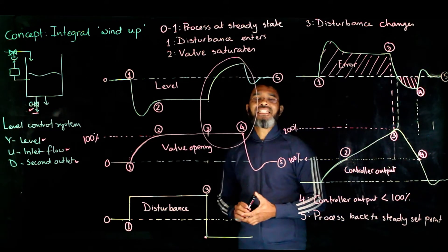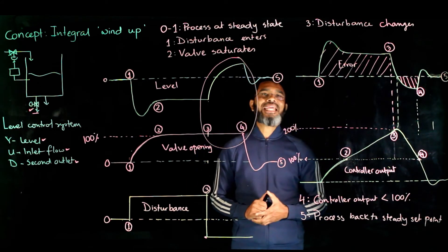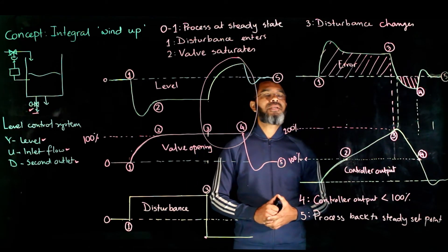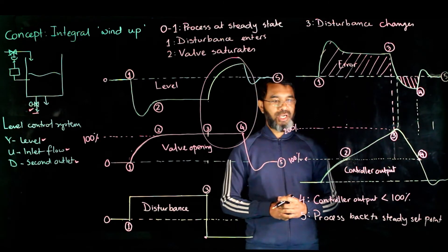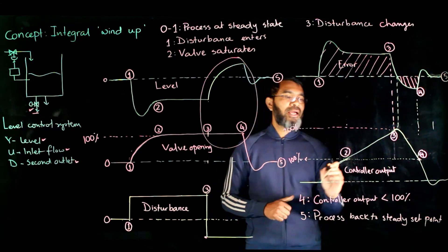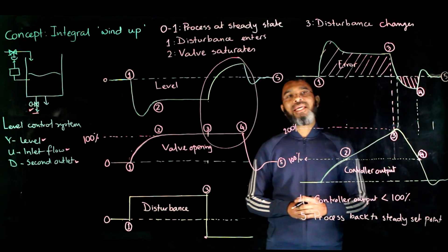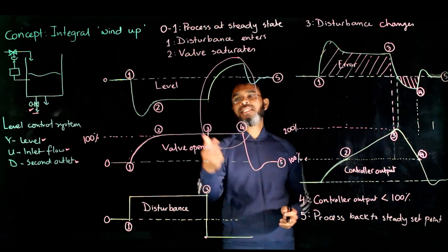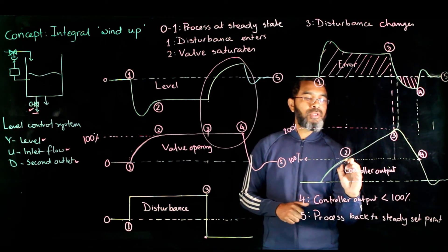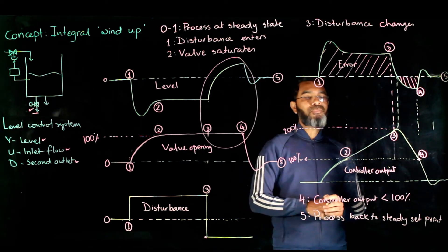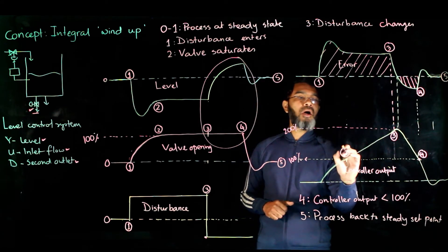This is the concept of integral windup — it happens because the integral action keeps increasing when there is a persistent error. The way to get rid of this integral windup situation is: when the controller calculates the control action beyond the physically realizable value — in this case 100% valve opening — the integral action is turned off.